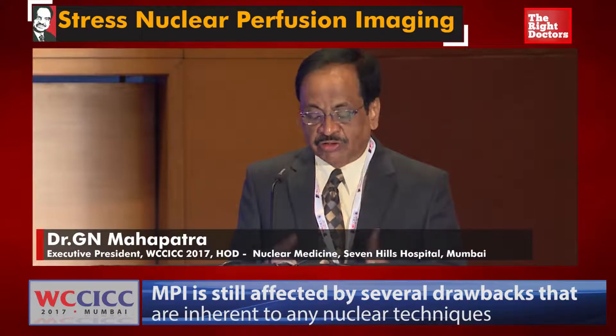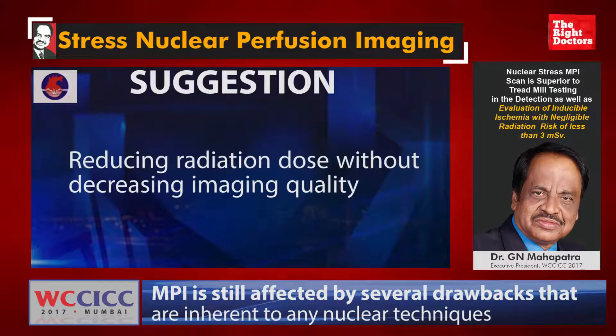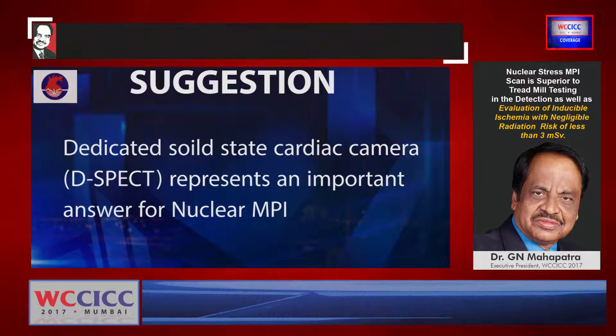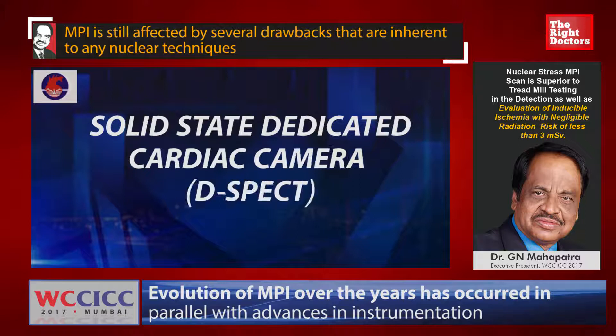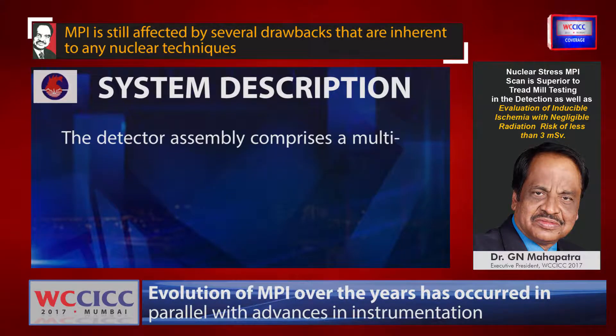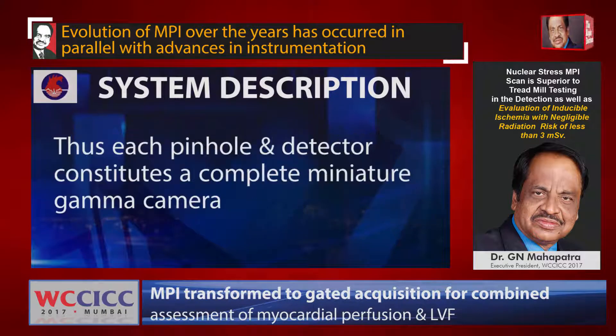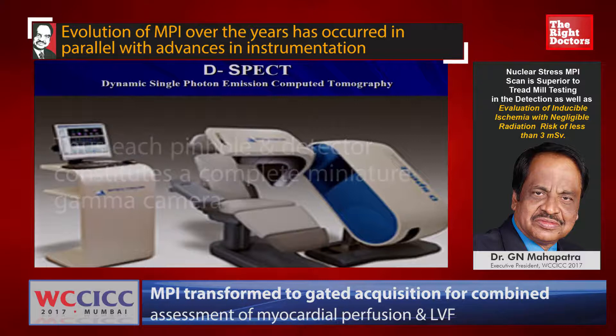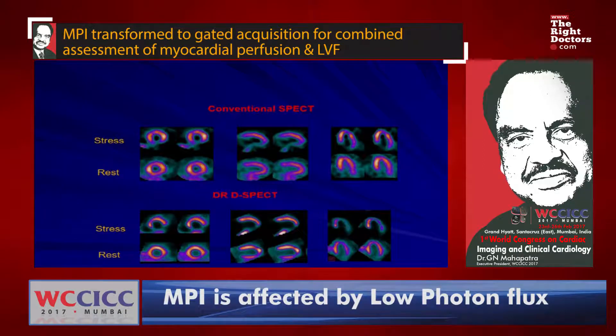The new generation solid-state detector gamma camera has now emerged. Its advantages include shortening the scan acquisition time and reducing radiation dose without decreasing image quality. The dedicated solid-state cardiac gamma camera D-SPECT represents an important advance for nuclear MPI, and is available in our country. The gantry is similar to a conventional gamma camera, but the detector assembly comprises a multi-pinhole collimator block where each pinhole illuminates a solid-state pixelated gamma-ray detector, so each pinhole-detector constitutes a complete miniature gamma camera. Imaging can be performed while the patient is sitting in a chair, and you can compare the image quality of D-SPECT with the conventional gamma camera — they are comparable.